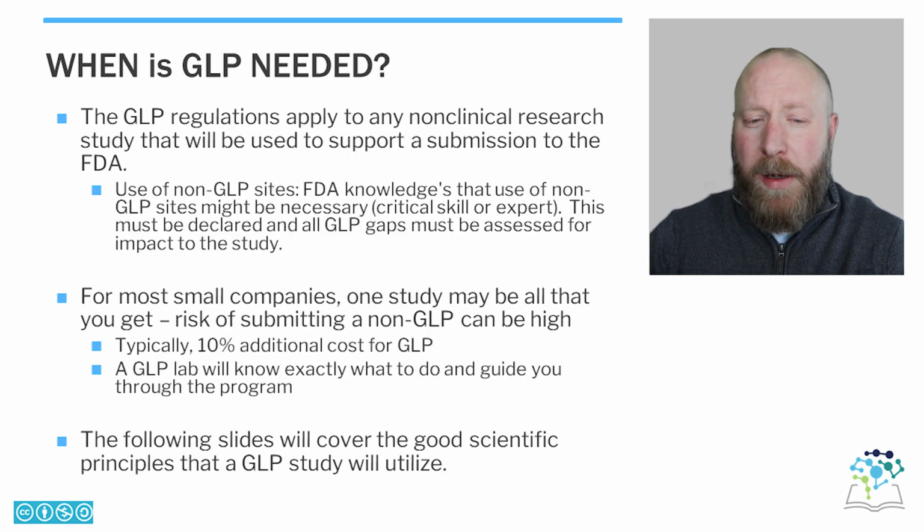So when is GLP needed? GLP regulations do apply to any non-clinical research study that is intended to support a submission to the FDA. Now, the FDA does acknowledge that the use of a non-GLP site may be necessary. This is typical when a specific skill or expertise is only available at a particular non-GLP site. If you do end up using a non-GLP site, you must declare these gaps to the GLP regulations and assess those gaps for overall impact to your study.